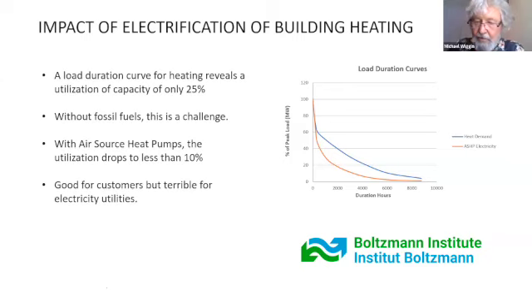Now, if you put in heat pumps, the peak is about the same. If you look at the electricity required for a heat pump compared to, let's say, electric resistance heating, they have a COP of 1 at peak load, roughly. So you still have to meet the same peak, but because of the efficiency during much of the year, the utilization drops down to about 10%. So for the incremental capacity you're going to install in your electric system to serve building loads, if you tell the electric industry they're going to install this capacity and only get 10% utilization, customers might like it, but it's terrible for the utilities. It's just a financial impossibility.